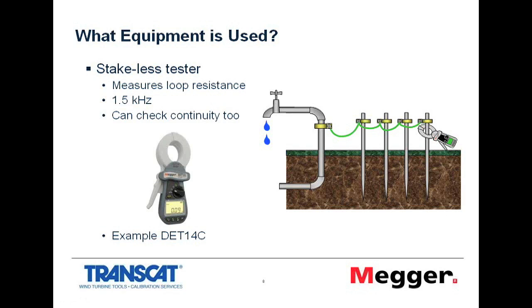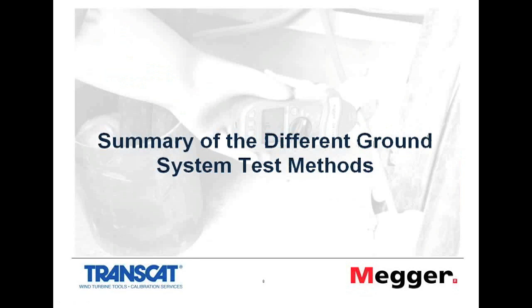It's also important to understand that the readings between this instrument and a 3-pole tester may not be exactly the same. However, this instrument will only ever read high, in other words, it won't ever read a falsely low reading. It will always give you a higher than the actual measurement. And also, the more paths in parallel, the reading drops to the actual value of this electrode. So it's great for applications where there are many current paths to ground. Okay, I'll move on now to the different test methods used.